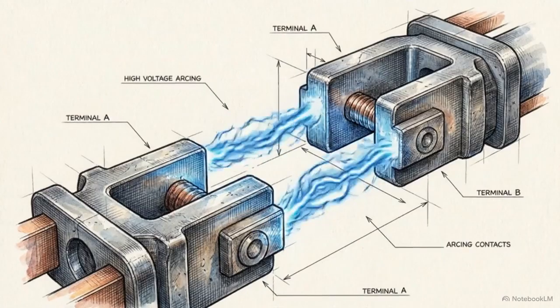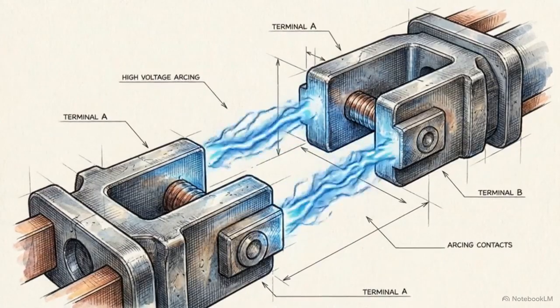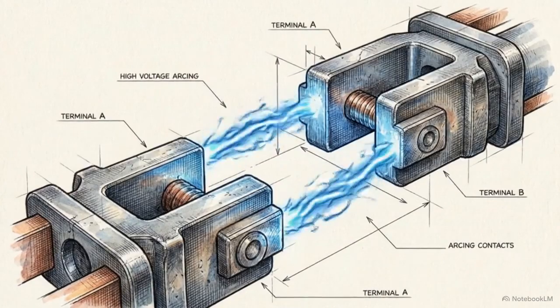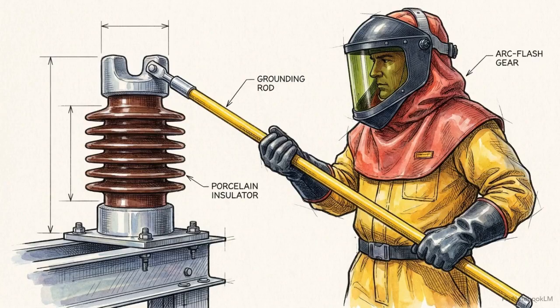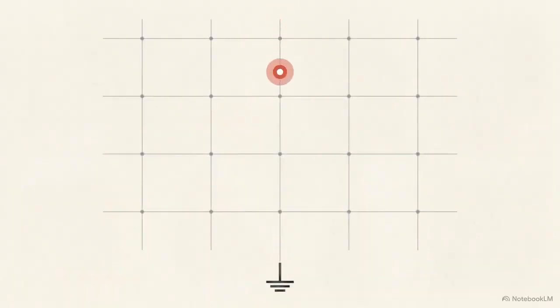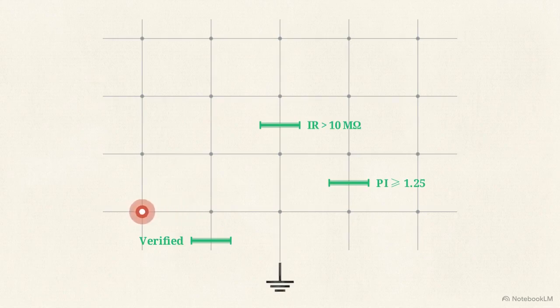Because the transformer holds a lethal capacitive charge after DC testing, the manual designates a strict hold point. Technicians safely discharge the asset with a grounding rod and visually verify the restoration of all earth links before proceeding. Dielectric testing mathematically proves the absence of invisible catastrophic paths to ground through the insulating barriers.